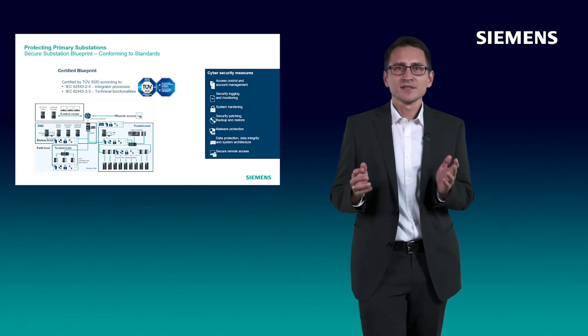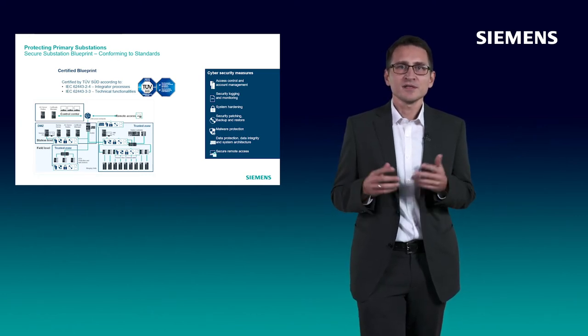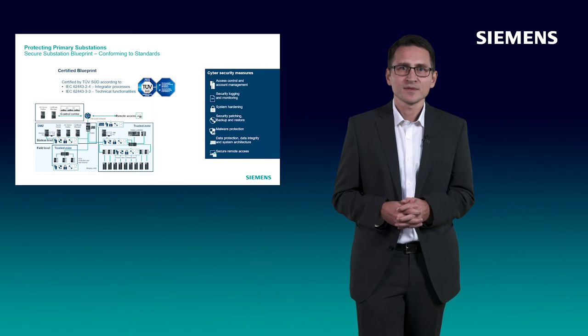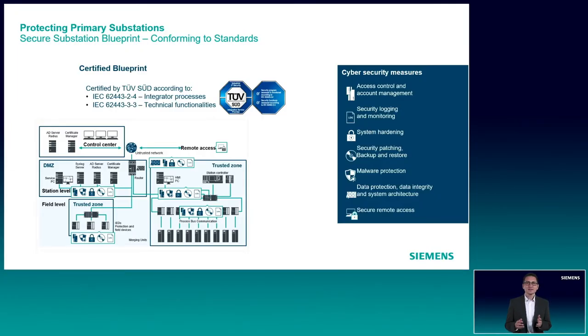As part of the holistic approach, we have developed a secure substation blueprint. It is based on the leading cybersecurity standard for industrial control systems, IEC 62443. The blueprint includes the system integrator process according to IEC 62443-2-4, as well as the technical solution according to IEC 62443-3-3.